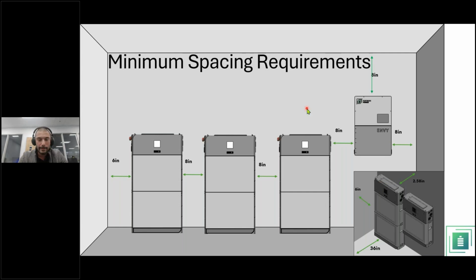Okay, minimum spacing requirements. This is more abstract, extracted from the UL testing, right? We gave 8 inches from eForce to eForce, and then 6 inches from eForce to wall, and then 8 inches from eForce to inverter.